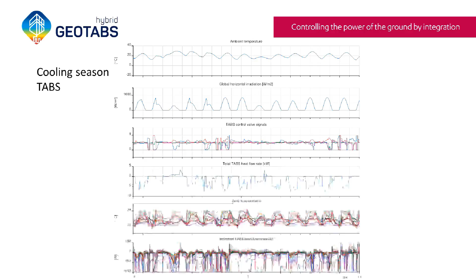What else can we see here? For instance, in this case, you see very clearly that two valves are being closed and one is being opened fully. So there is clearly some cooling demand at this point, but just for one floor, and only one floor is actually being cooled, which also drives down the total energy cost of the building.